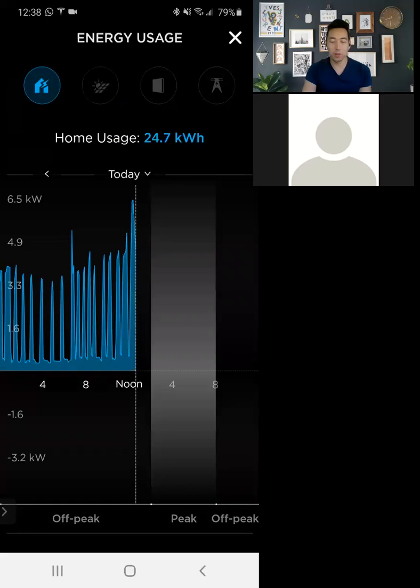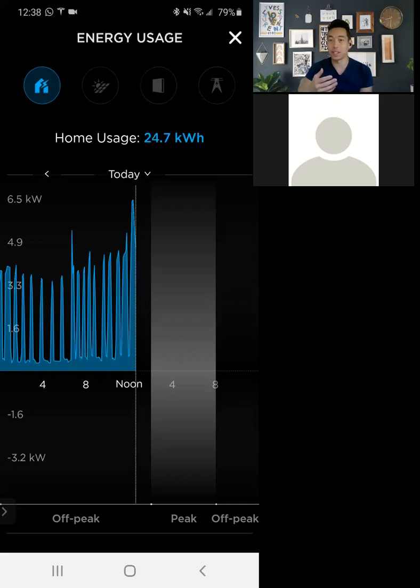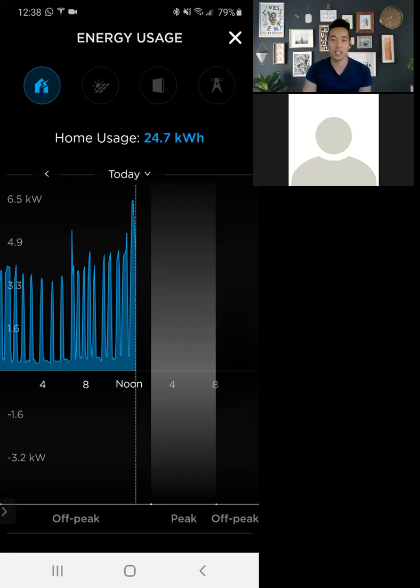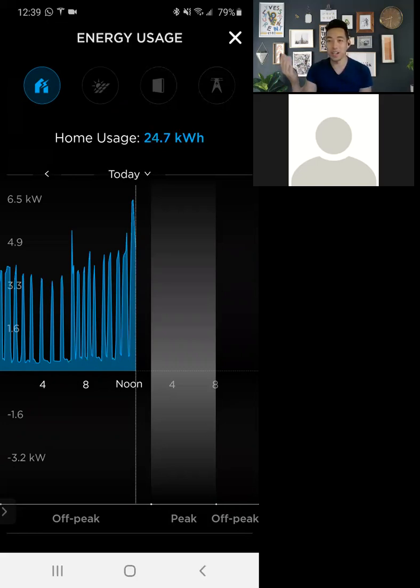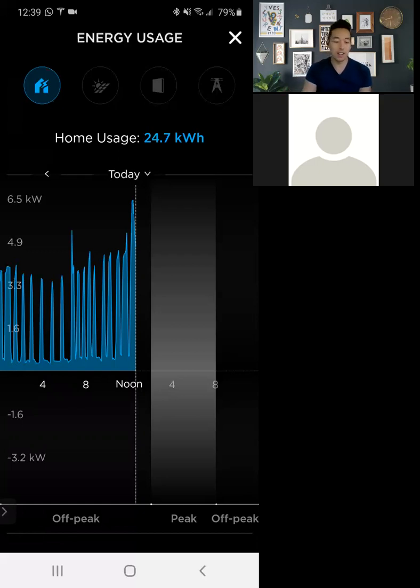So if we take off solar, this is just the AC basically turning on and turning off, turning on and turning off throughout the day, probably every 30 minutes, it runs for 15 to 30 minutes and then turns off for 15 to 30 minutes. And that's what you're seeing. And there's pretty consistent throughout the day in the summertime. This is just what we're seeing. I have a really old 18 year old one stage AC. So if you have like a variable AC or two stage AC, this would look very different, but that's what you're seeing for me.